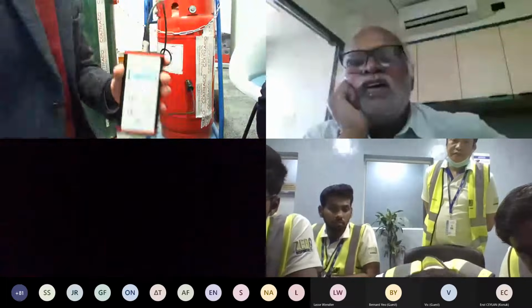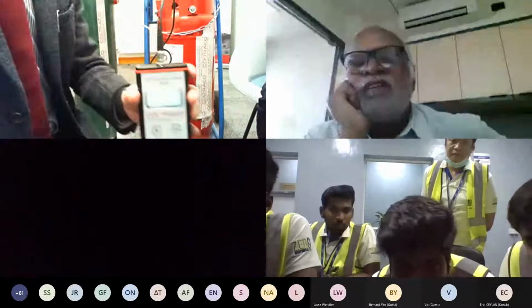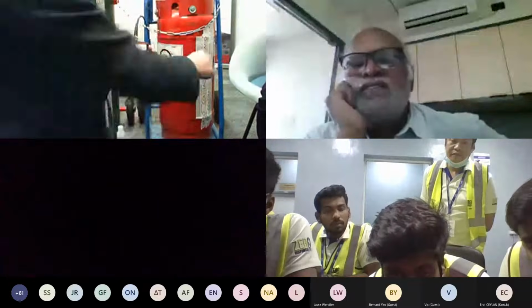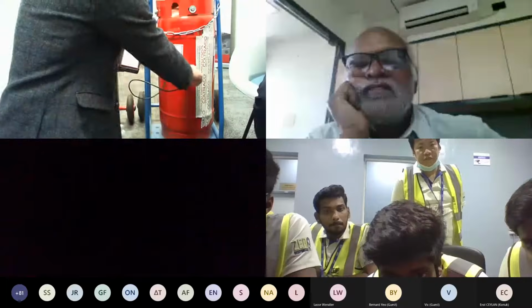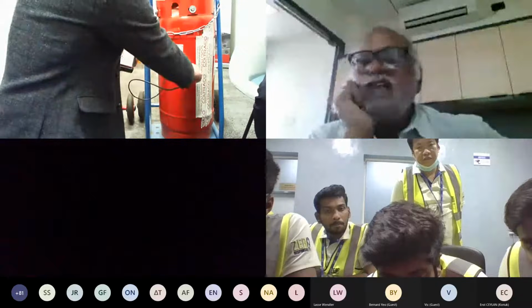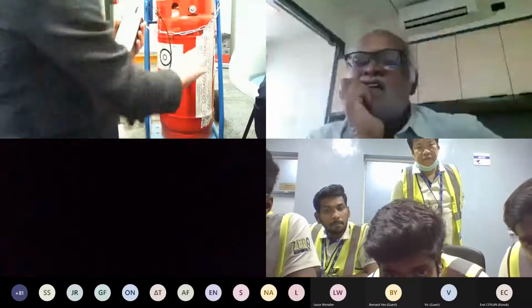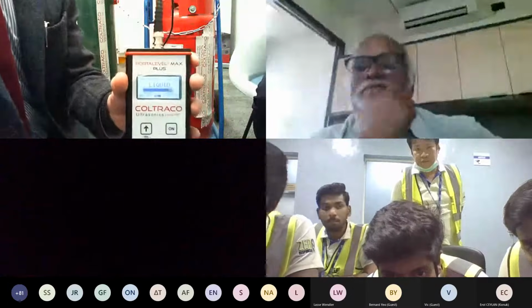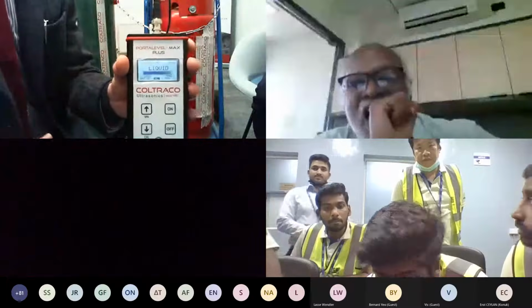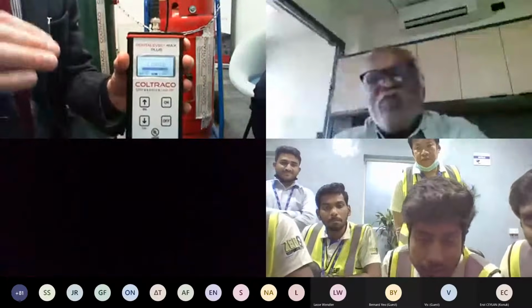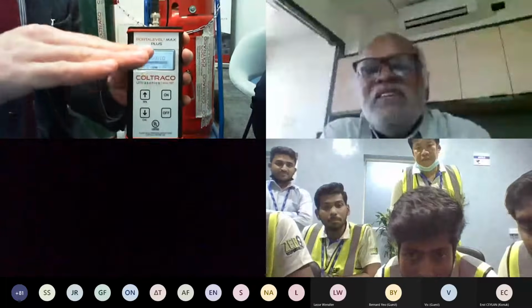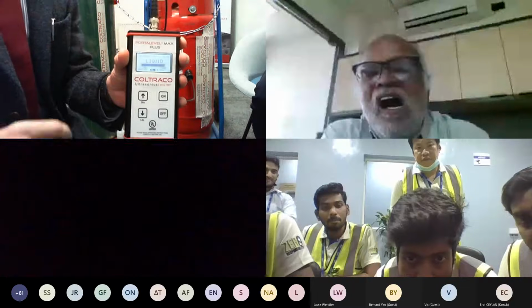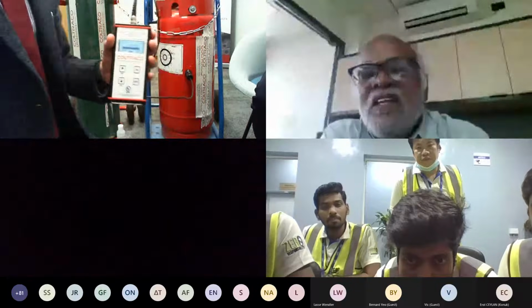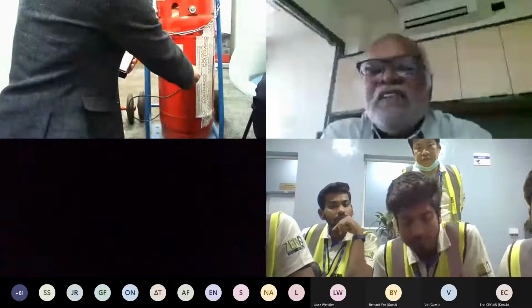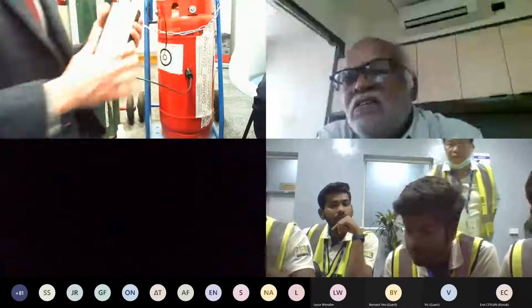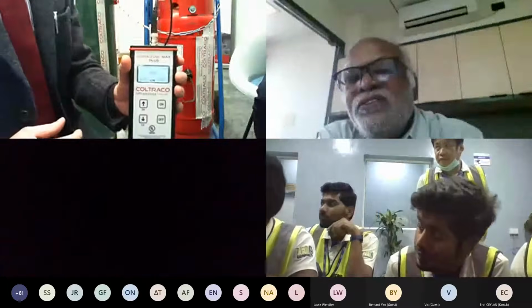So still on liquid. Now showing gas. So I'm going to move down in very small steps till I get the exact point that it changes. This part here, as you can see, it's fluctuating. You can see the bar graph is oscillating slightly. That's a good indicator that you're right on the liquid level. That's the liquid level itself, perhaps oscillating very slightly past the center of the sensor, which means it's very likely exactly on where it is. So what I'll do now is lift it slightly until it's there. You see it's just changed over to gas, exactly there.